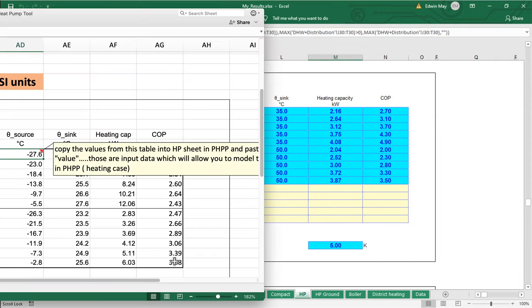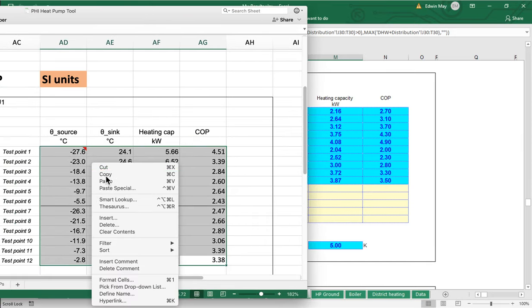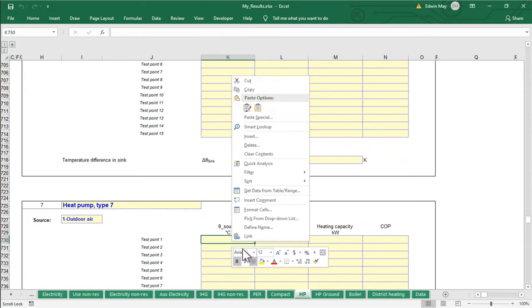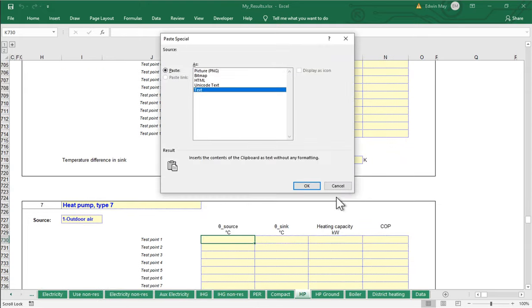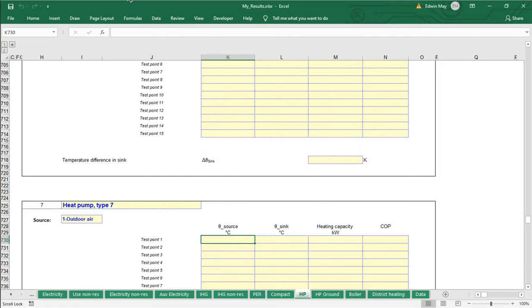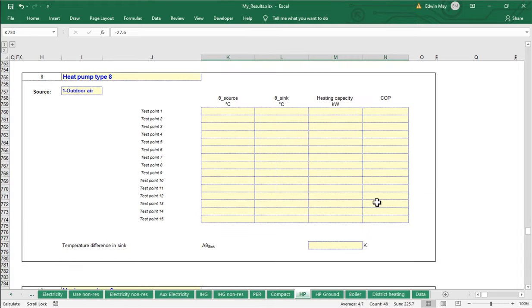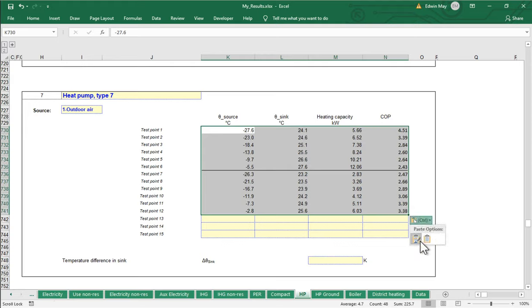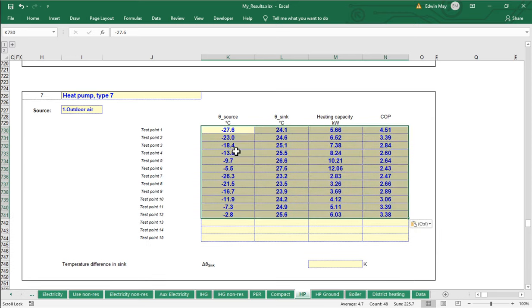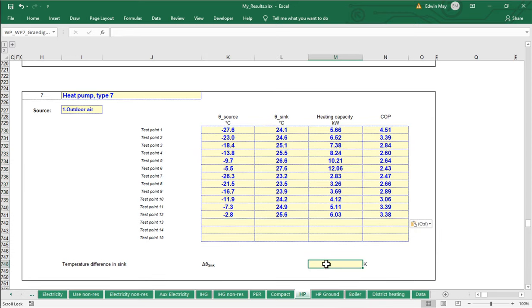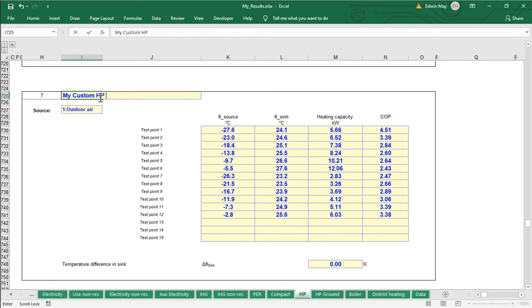The idea is you grab all of that data, copy it, then come into the PHPP and paste it — using 'paste special, match destination formatting.' We should enter zero for the sink temperature for all these custom heat pump entries, and then we can name it whatever we want, such as 'my custom heat pump unit.' We now have a custom performance profile based on that heat pump worksheet.